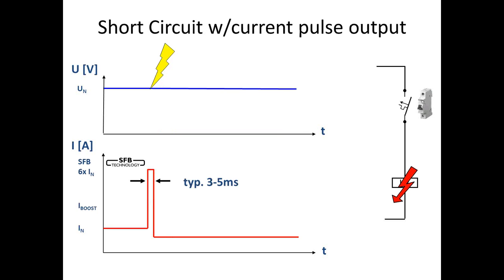To get a thermomagnetic breaker to trip, a power supply must be sized correctly once again. A power supply needs to be able to supply 6 times the nominal current rating of the breaker to trip it in the magnetic area of the breaker curve. So, for example, a 4-amp breaker requires 24 amps to trip.